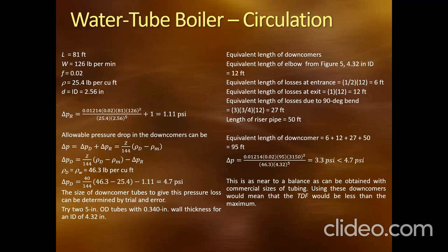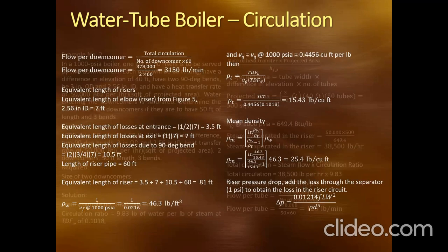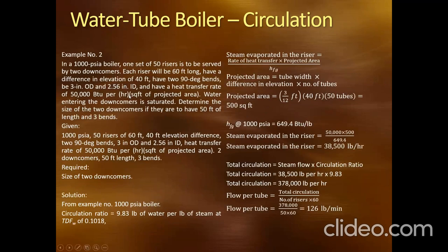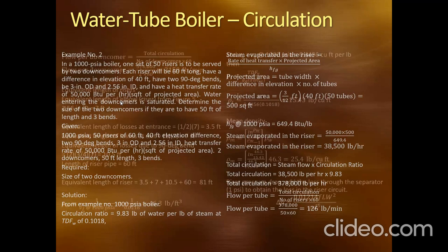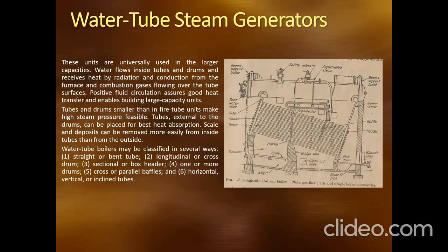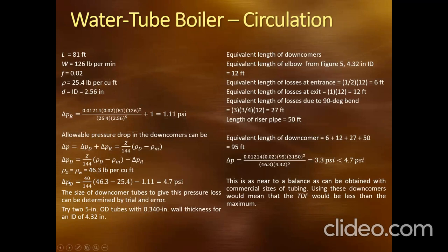Now, the allowable pressure drop in the downcomers: delta P equals delta P_D plus delta P_R equals Z over 144 times rho_D minus rho_M. So, delta P_D is equal to Z over 144 times rho_D minus rho_M, minus delta P_R. Rho_D is equal to rho_W, 46.3, because it is water on the other side, the downcomer, purely water. Where does the 40 come from? Here, elevation 40. The tube bends, so that is different; it is the elevation, not the length of the tube.